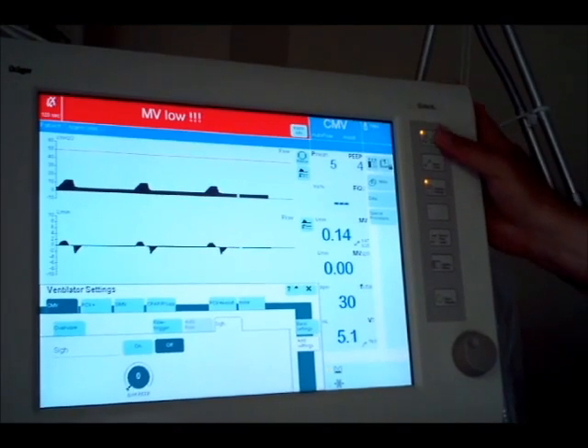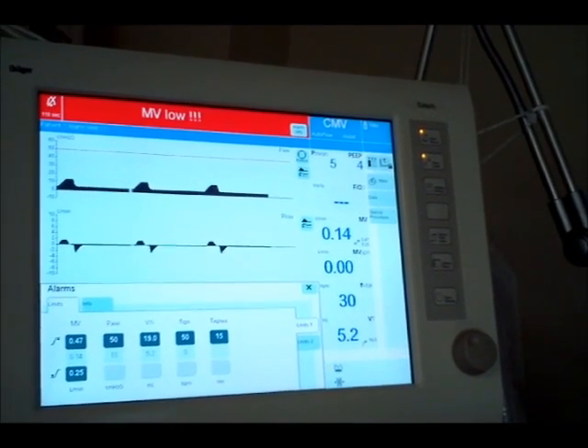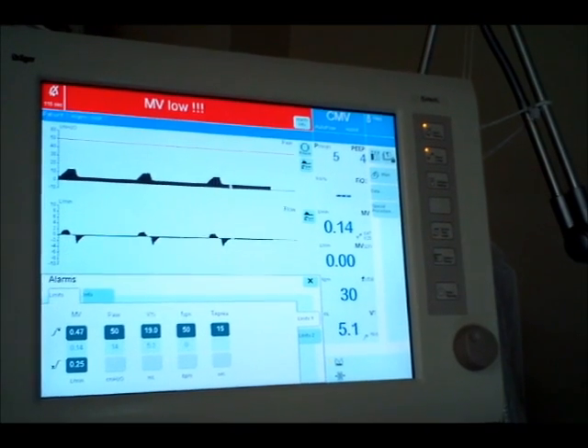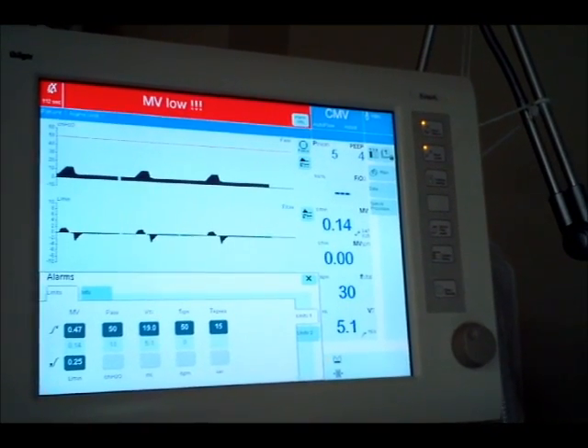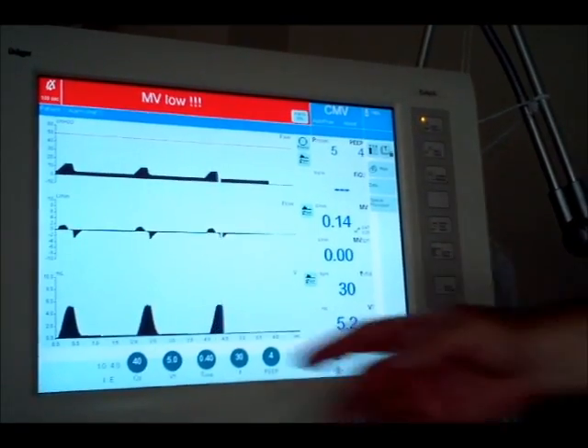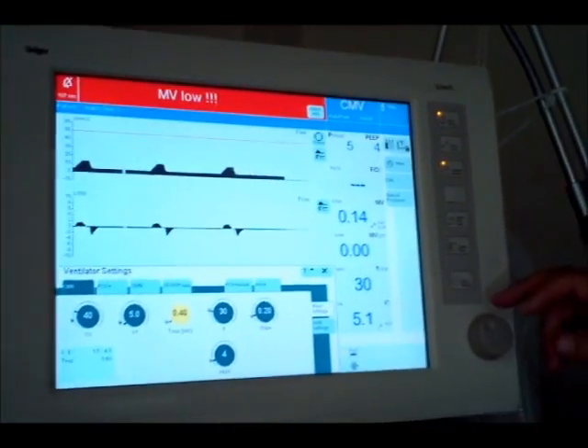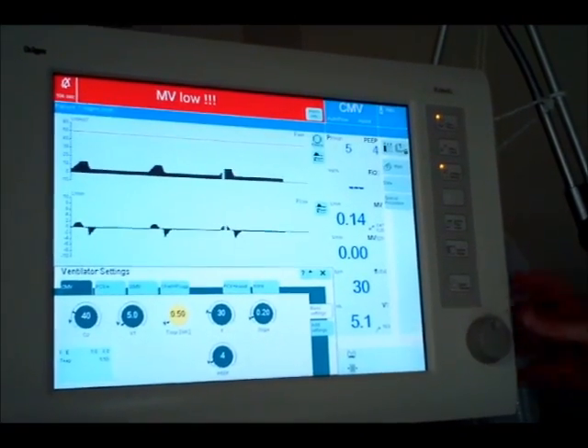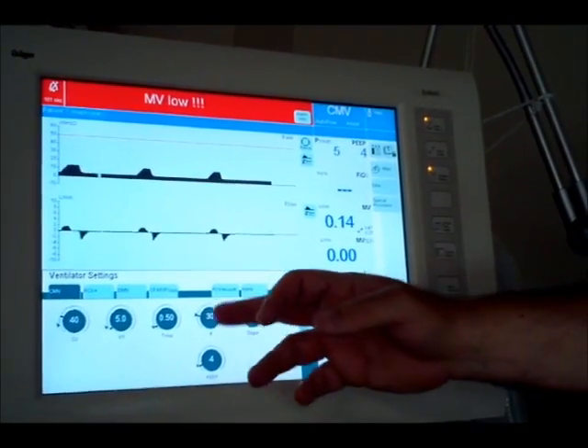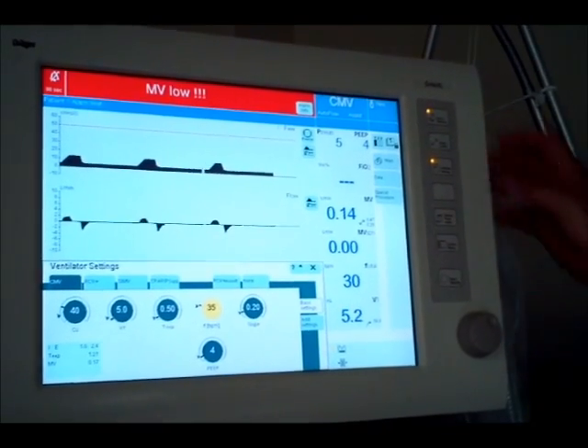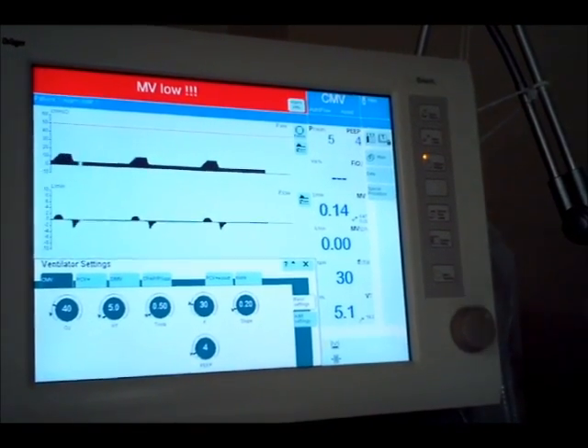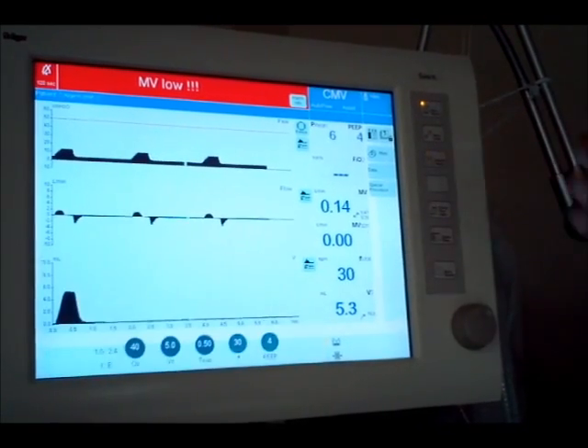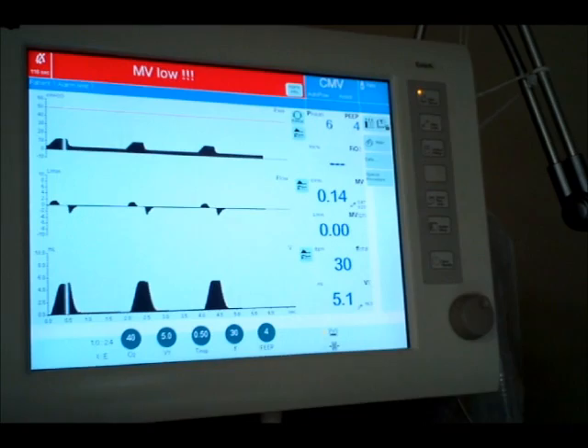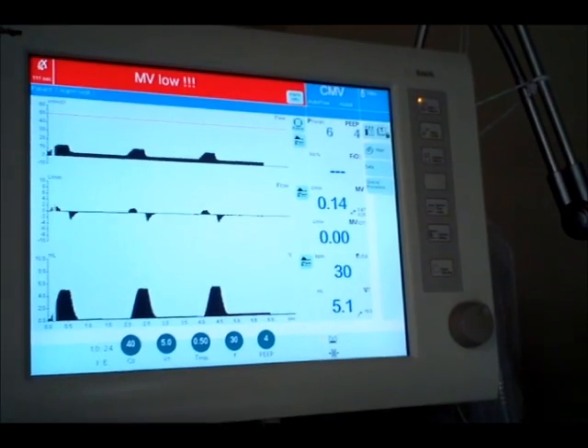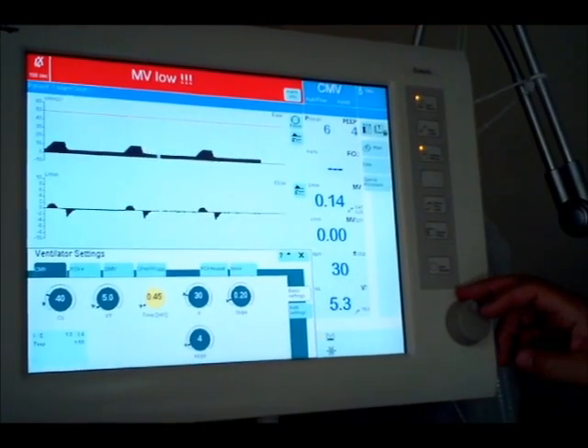Sometimes alarms, the alarms are obnoxious always, but I will warn you a little bit. Sometimes people want to address the alarms and they've forgotten to do something. So a good example, I'll show you kind of what might happen that you really don't want to happen. Let's say you're making a change. Say you change the inspiratory time to 0.5, and we're supposed to change the rate to 35. And then your alarms go off, and you don't like that noise, so you go back and readjust your alarms. Well, you forgot to confirm your rate. So just make sure you double check. It doesn't really take that long because you can bring all the settings up. Let's go back to our initial settings here.